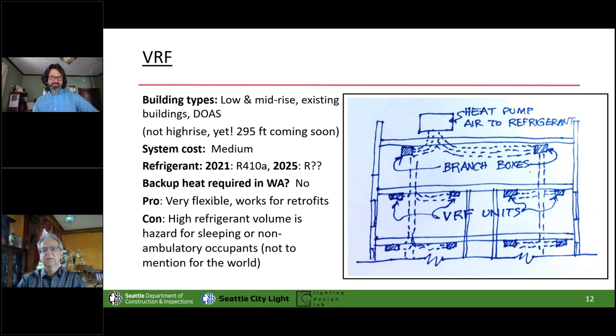Now, VRF. You could see in the cartoon that we're just taking heat out of air, which is what's so cool about a heat pump: air that's already really cold outside, if you compare it with Fairbanks, still has a lot of heat in it, and you can pull that heat out and put that heat inside directly with the refrigerant. Those branch boxes that it flows to can start pumping refrigerant down to the VRF units, heating one and cooling another at the same time, even coming from the same branch box. Is that right, Ben? Yeah, they can move heat around within the space. They basically use the compressor almost like a pump to move refrigerant and therefore heat. So you could have one space that's heavily shaded. It's an October morning, and the next space over has sun coming in, and it handles them both nicely.